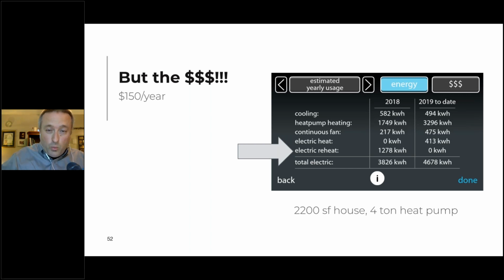So the house was still wet from the slab drying. I got a phone call about a $130 or $150 electric bill when they weren't there, and it was the reheat doing it, but it was a setting problem. I had set it to 46% relative humidity, which was too low for 70 degrees. It would have been fine at 75. In fact, it was, because you can see 0 kilowatt hours on the electric reheat line for 2019.